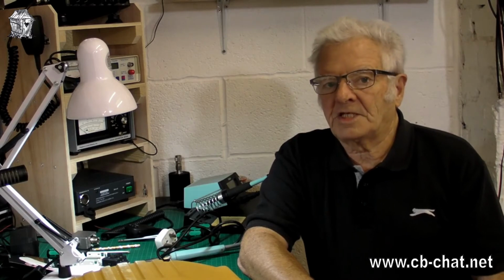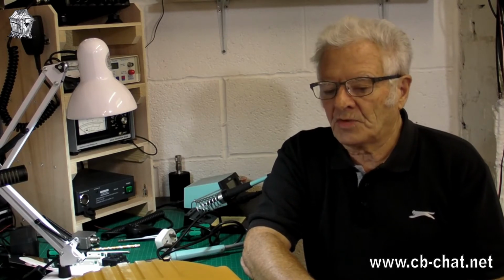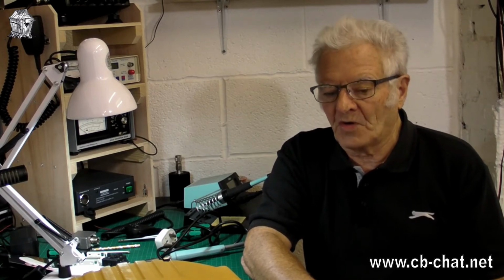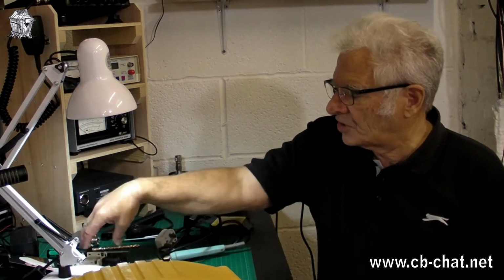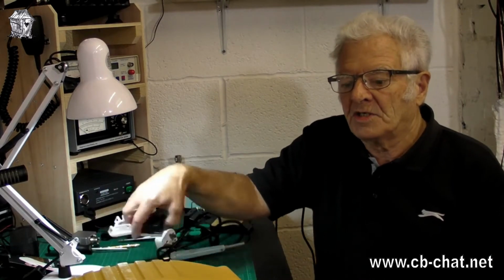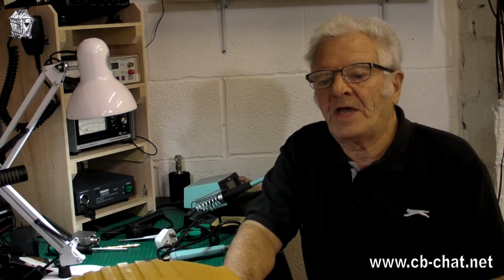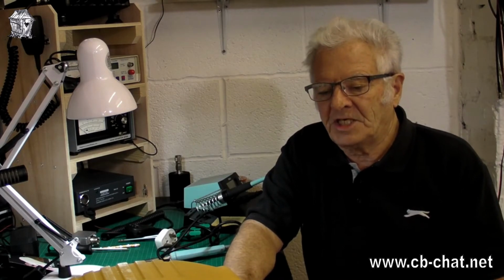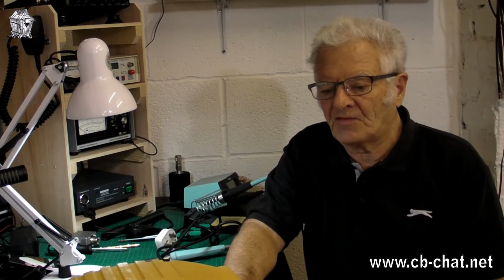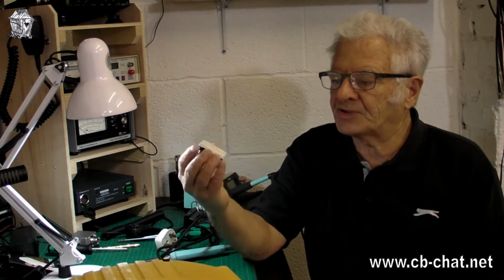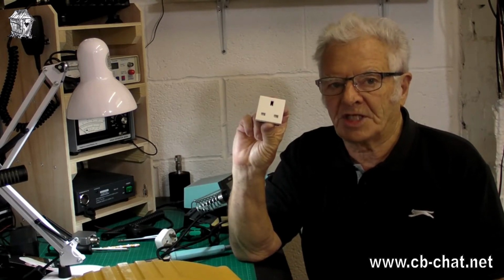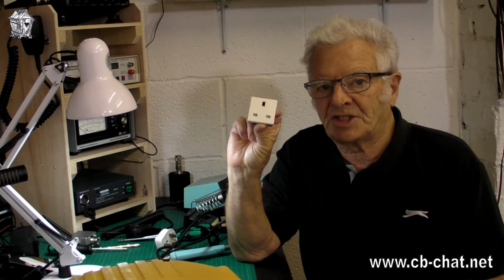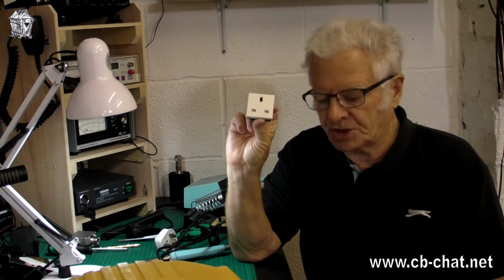And that is what I got. I bought one of these PAT testers. I've had loads of them over the years, and I've just got another one. And this one, the PAT tester, failed its PAT test. It failed its safety test itself, because the 13 amp socket that you have on these things, which you're supposed to plug your appliances into to test, was loose.